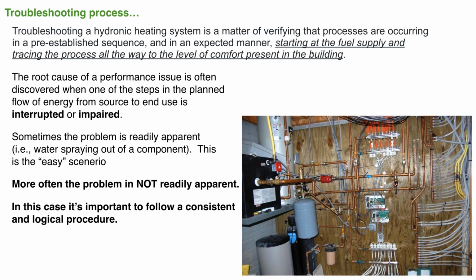But oftentimes it's more complicated because the problem is not readily apparent. So now we've got to go to this step-by-step procedure and try to logically trace through what that system is supposed to do until we find something that is supposed to happen that isn't happening. And I put down as a close on this slide, don't always blame the boiler. Oftentimes, homeowners or building owners, if something isn't comfortable in the building, say it's the boiler's fault. Well, more times than not, it's actually not the boiler's fault. It's something else in the system. Maybe it's a zone valve or a relay or a plugged filter, or maybe a 4-year-old got in the mechanical room and likes the look of that nice red handle on that valve and has shut it.